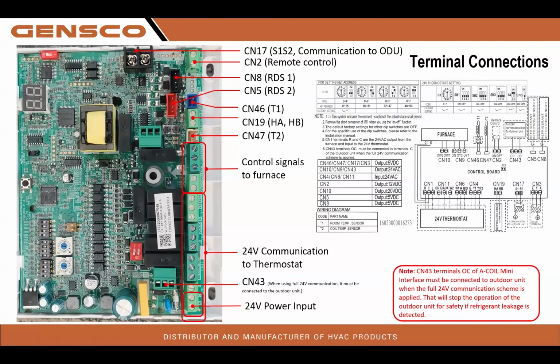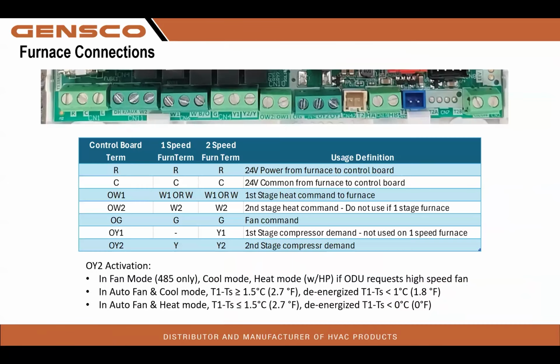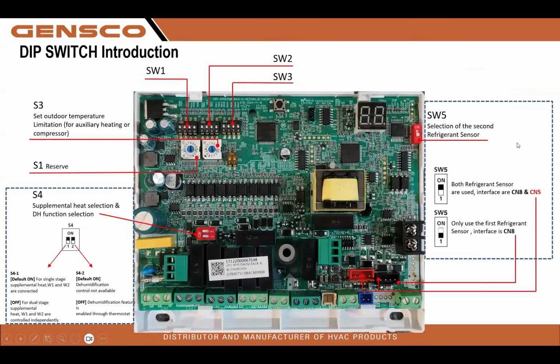All of this is in your installation manual. Here is another look at our terminals: RC, W1, W2, OB, Y1, Y2, OW2, OW1. This is where we're connecting our thermostat and our T2 sensor and S1, S2. This has to do with the refrigerant leak detector. It must be plugged into the black port, and SW5 must be in the off position. Our dip switch selections.